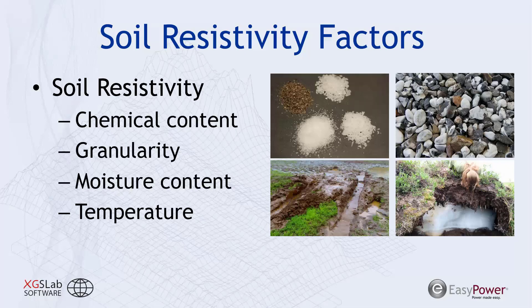Typically, when someone goes out and evaluates the resistivity of soil, they're looking at a more macro level — examining the chemical content, granularity or particle size, moisture content, and temperature. Understanding what contributes to greater electrolytic conduction helps us estimate what will reduce or increase resistivity. For example, higher chemical content and higher moisture content allow more charged ions in the material, yielding lower resistivity.